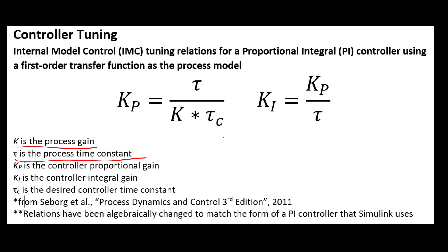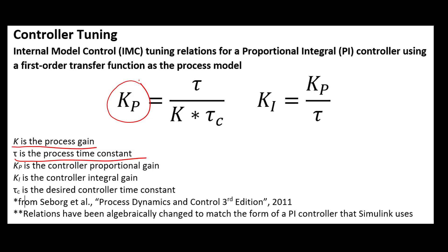If we want a less aggressive controller, we could choose tau_c on the same order of magnitude as the process time constant, or even larger. The parameters tau and k are obtained from data and measurements of the system — they are not tunable. Tau_c is what we pick, and it allows us to calculate kp. The integral gain ki is then calculated as kp divided by the process time constant.